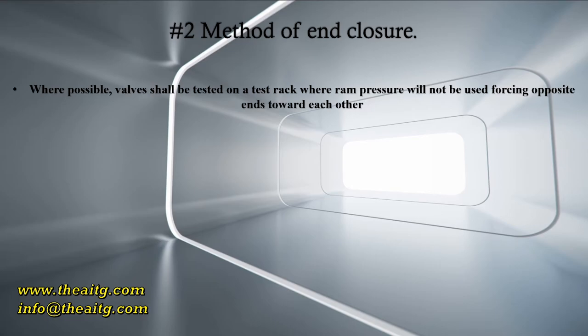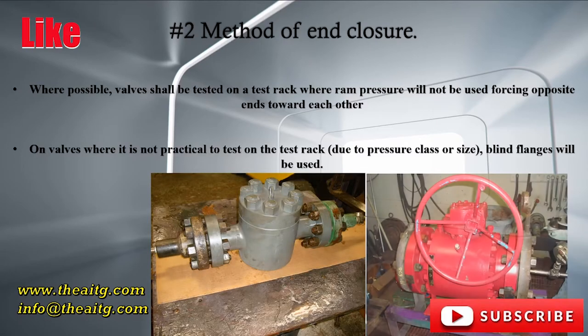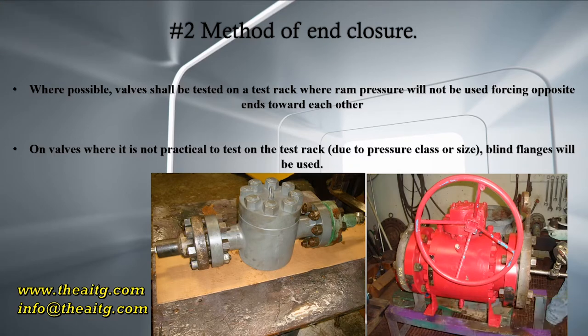Method of end closure: where possible, valves shall be tested on a test rack where ram pressure will not be used forcing opposite ends towards each other. On valves where it is not practical to test on the test rack, blind flanges will be used. From these photos you can see blind flanges being used to perform the hydrostatic test.